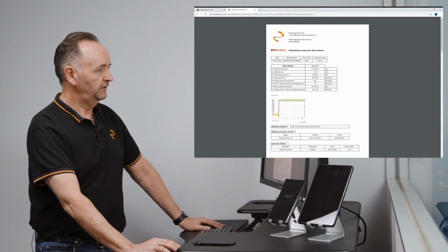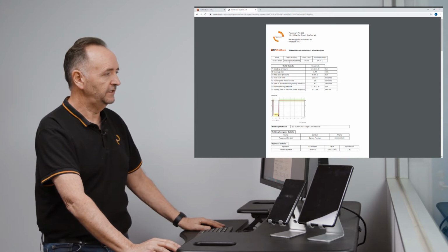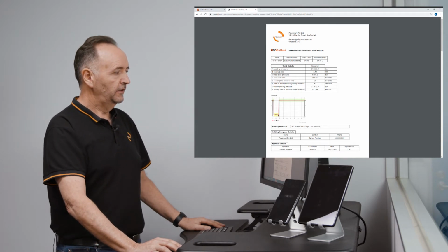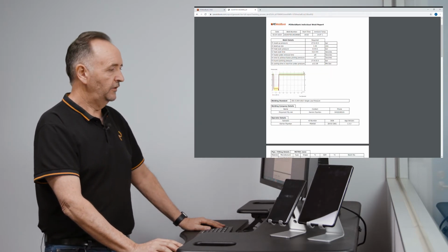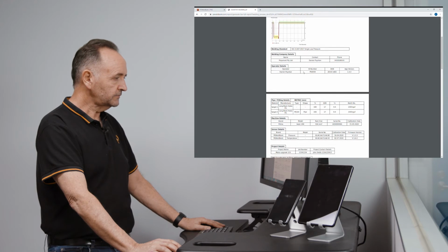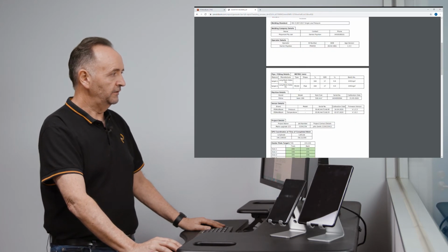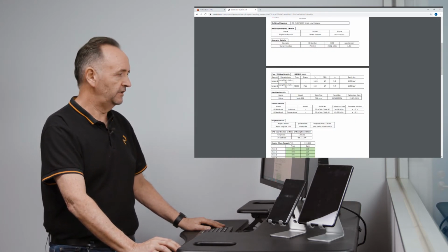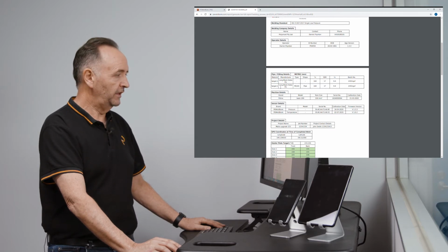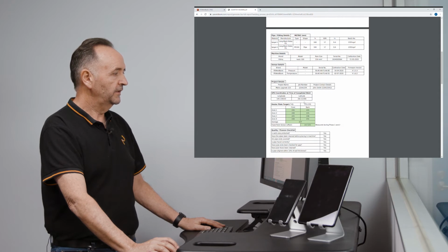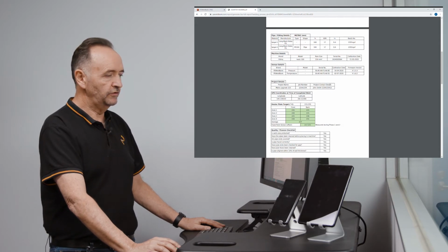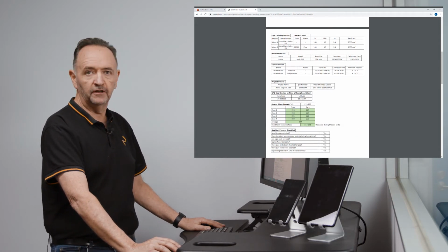So this one here, you can see in this 4-page report, you've got the date, your weld number, start time, and all the information you require in a report. There's actually more here than what you'd generally be asked for. Here we've got the welding company details, operator details, pipe and fittings, the manufacturer's information about your pipes, machine details, sensor details, project details, GPS locations.